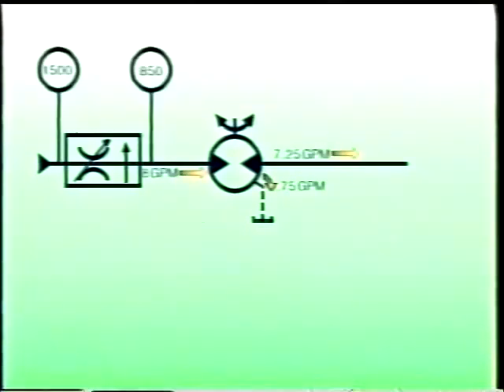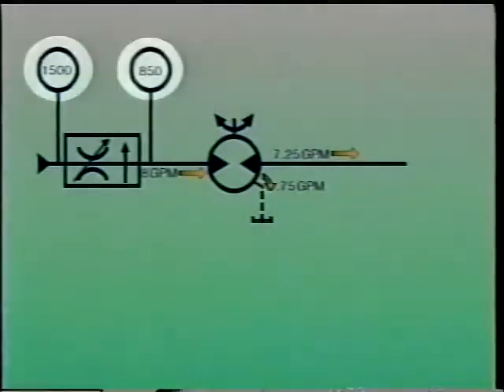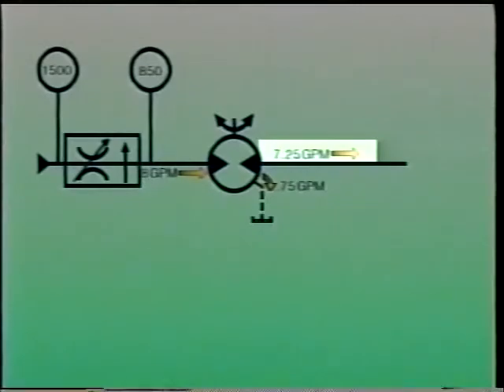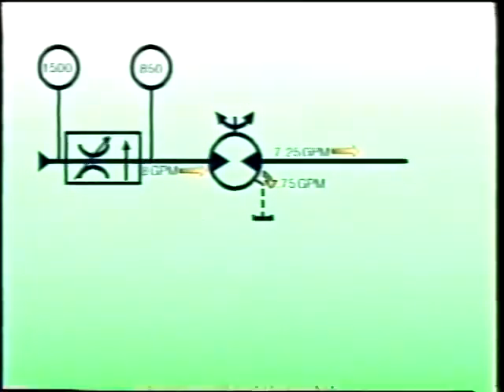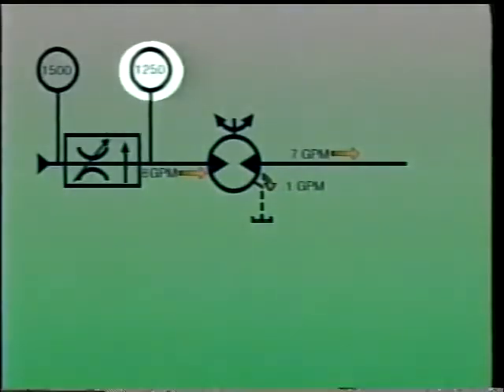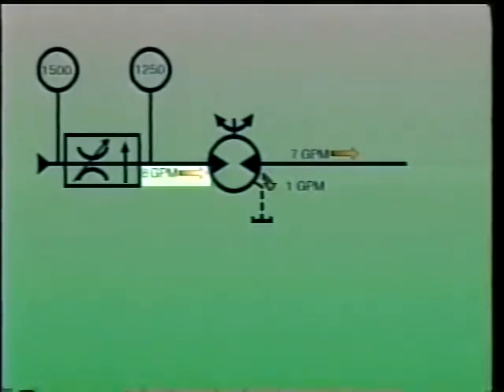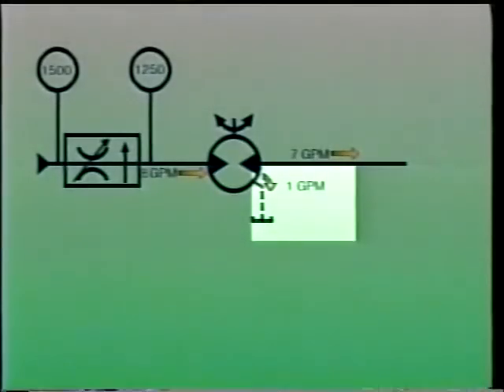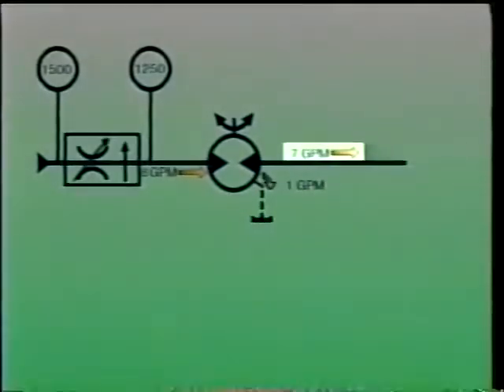Meter in circuits do not work well for similar reasons. For example, a valve in this circuit reduces the motor inlet pressure from 1500 psi to 850 psi. If leakage from the motor is three quarters of a gallon per minute, then the speed of the motor will be based on seven and one quarter gallons per minute. If the load pressure on the motor increases to 1250 psi, the valve will maintain the same flow rate into the motor — eight gallons per minute — however, since pressure inside the motor will be higher, leakage will be greater, perhaps as high as one gallon per minute. As a result, only seven gallons per minute pass through the motor and it will slow down.